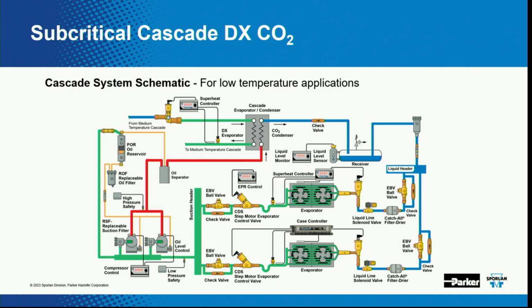In the last slide, I had a pump. In this slide, I don't have a pump. I have compressors. This is a receiver tank coming out of the heat exchanger, and we're pulling the liquid off the bottom and feeding it to the cases. Those go through an expansion device. Here I'm depicting an electric expansion device going into the evaporator, doing full DX heat transfer and going back as vapor to the compressors, because the compressors only compress vapor. Those compressors bring it back up to temperature and pass it back through the heat exchanger, and the cycle continues. This is mostly for low temp, because we need that compression to get the delta and the lower temperature we're looking for.